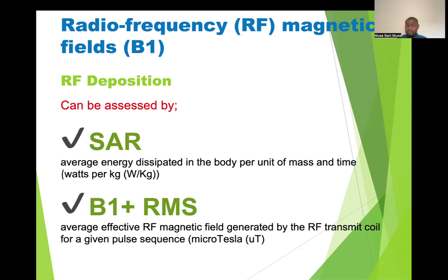Whereas we've also got B1 root mean square. So how does this come into effect now? With specific absorption rate, taking accurate readings of the patient's weight and height is really important. I know some people used to be like, oh, well, roughly I weigh this and that. No, you need to know the accurate weight and height of the patient, because this is what the scanner uses to calculate the RF energy deposited into the body. You do not want to overheat your patient. Trust me, you do not want to, because some patients have certain implants, some have temperature control issues, or for example, you've got pregnant patients, whose temperature is usually already high.